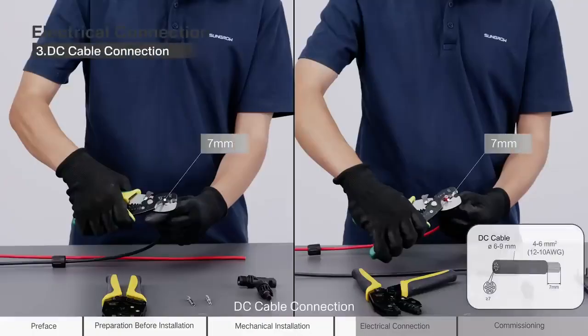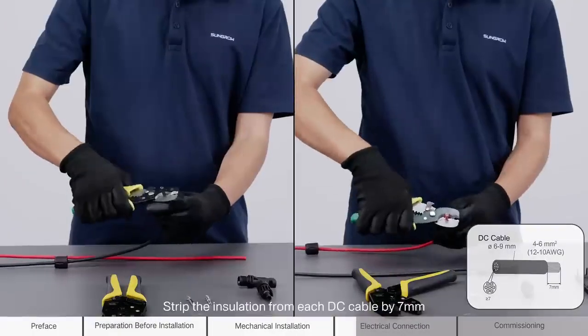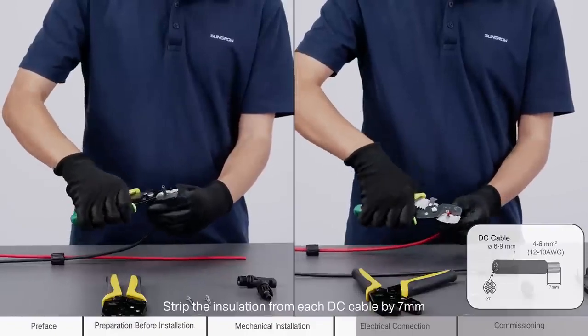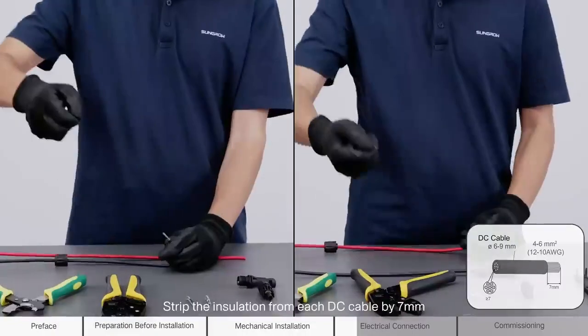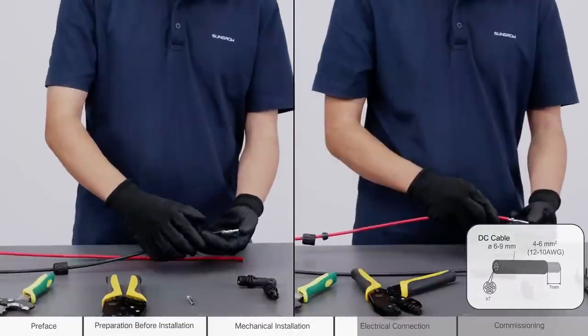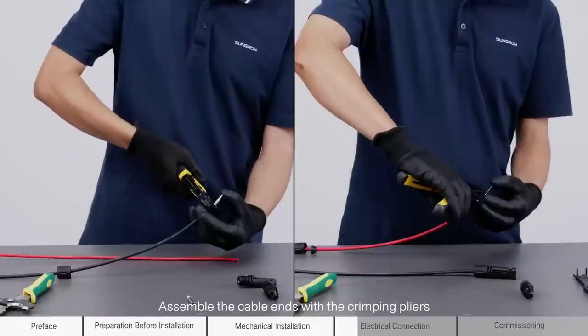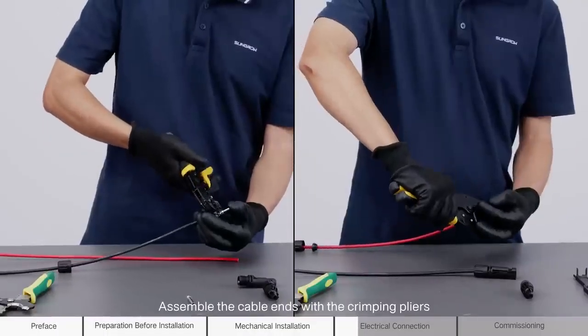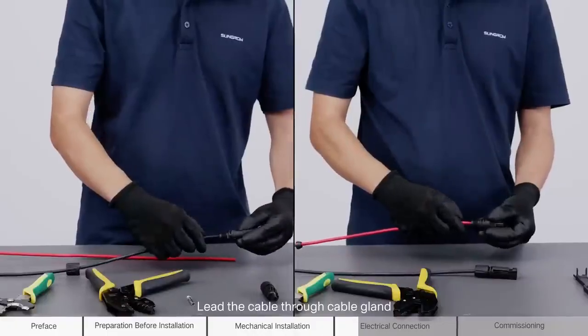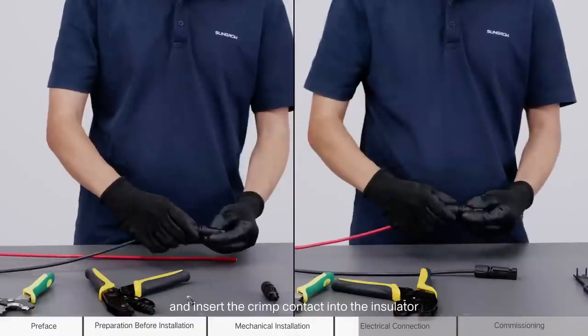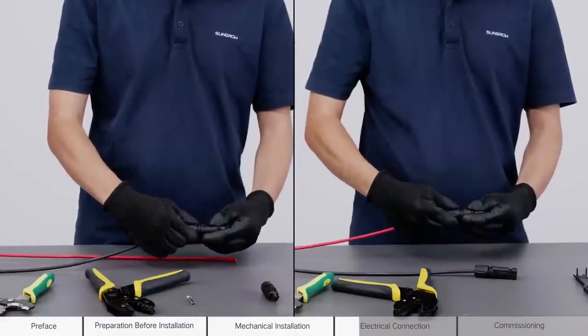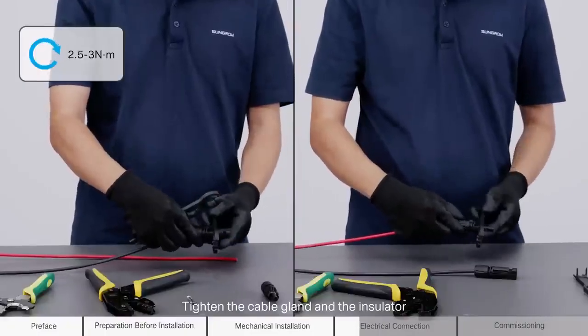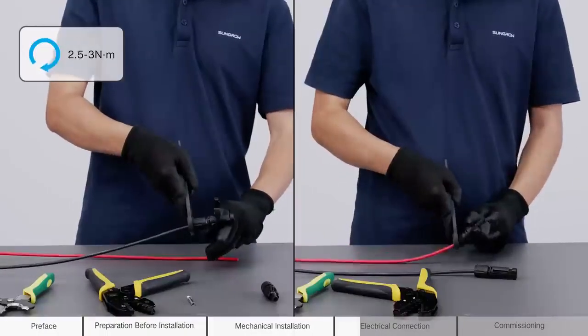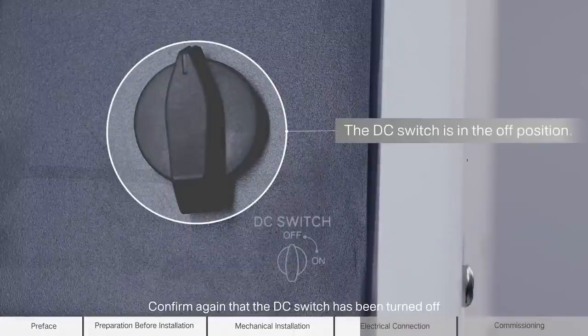3. DC cable connection. Strip the insulation from each DC cable by 7 mm. Assemble the cable ends with the crimping pliers. Lead the cable through cable gland, and insert the crimp contact into the insulator. Tighten the cable gland and the insulator. Confirm again that the DC switch has been turned off.